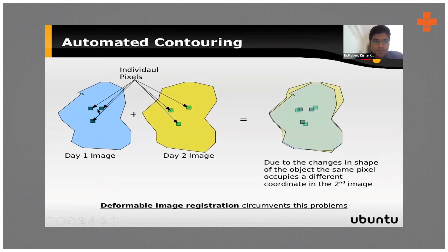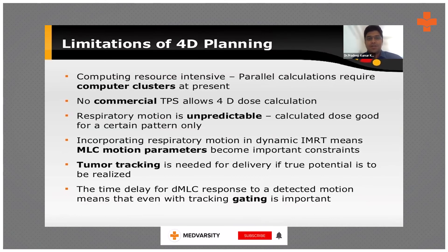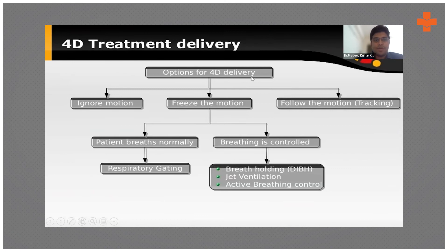Daily variations at the individual pixel level are recorrected using automated shifts before delivery. Tumor tracking is a known limitation, and gating has been incorporated alongside 4D. With 4D alone, the time delay in detecting motion limits its value unless margins are being reduced. Gating means the patient is asked to hold their breath during inspiration, and the beam is delivered only during that period — targeting one particular zone of motion. 4D delivery can be done by ignoring motion, gating to freeze motion, or continuously tracking motion.